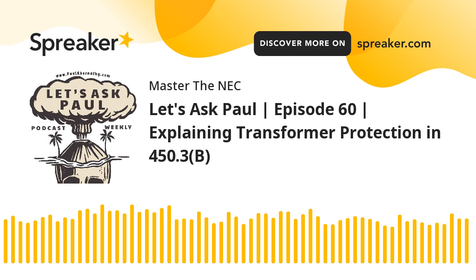So a 2 kVA transformer would be 2,000 divided by 240. Much smaller transformer, that's 8.33 amperes. That is my primary current. Well, in that case, it would fall under the 9 or less. Or less than 9, I should say. Less than 9. Not 9, but less than 9.